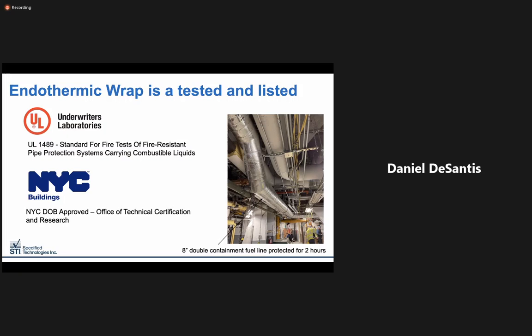E-wrap is also recognized by the New York City Department of Buildings Office of Technical Certification and Research as an approved method of fire resistance enclosure for fuel oil lines. This 8-inch double containment fuel oil line is a good example of a use case where a finished ceiling height was a major consideration. With traditional methods of enclosure, you would lose considerable height. In this case, the piping is isolated and protected without the need for drywall. It's a great solution for rooms like this crowded MER.